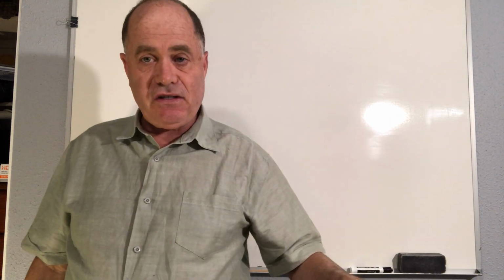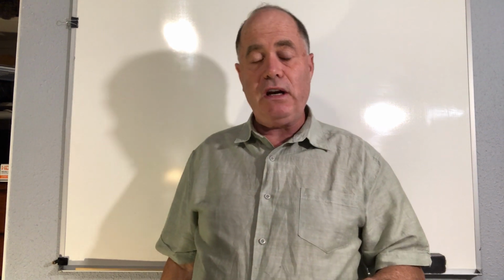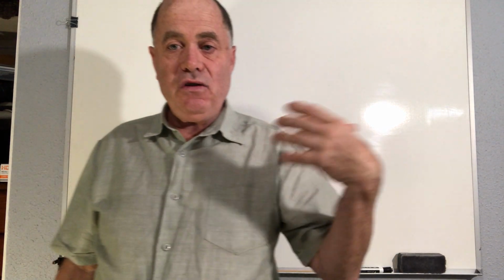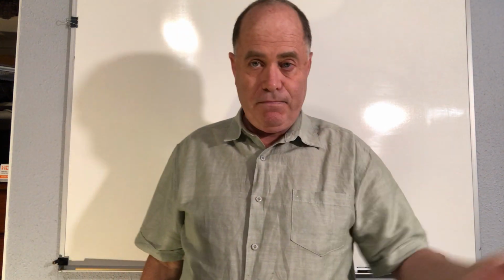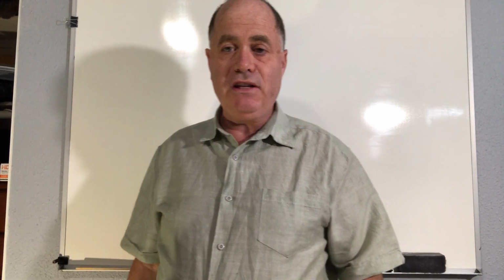All right. Now here we go. Let's go to, again, electrical power. Again, you have to have a means of disconnecting it right next to the equipment so you can make sure that you shut it off and lock and tag it out. And then you need to have an outlet nearby so that you can plug your vacuum pump in, your recovery unit, your drop light in case you have to work while it's dark.